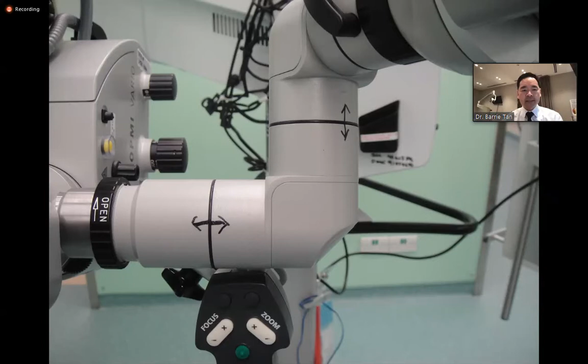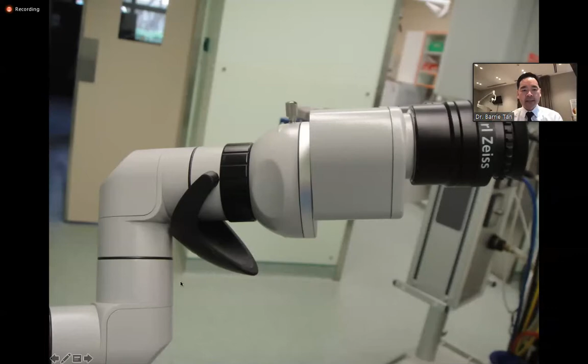it should remain perfectly weighted. And the ideal movement should be that with a little movement of your forehead against the lens or eyepiece, you should be able to just move the microscope lightly. And the eyepiece should not swing up and down wildly when you press the release button, for optimal balance. Again, this is an example of a side viewing arm of the operating microscope.